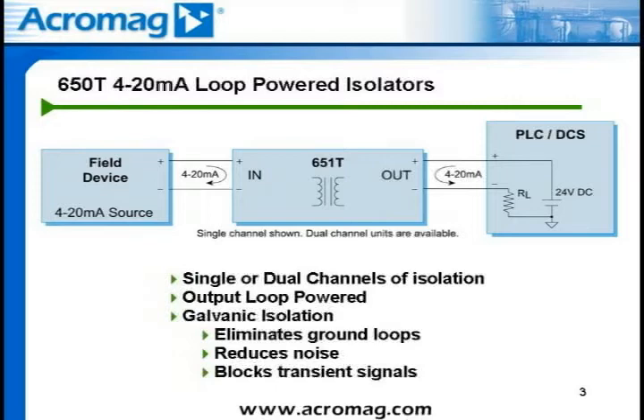One application would be where a field device is sourcing a 4 to 20 milliamp DC signal, and this signal is to be an input to a PLC which is also providing power through an internal 24-volt DC source. In this case, both the field device and the PLC are trying to power the analog loop — this will not work. A two-wire isolated transmitter is required to correct this power problem. The 651T will take the sourced 4 to 20 milliamp DC input signal and provide a sinking 4 to 20 milliamp DC output signal, enabling the 24-volt DC power supply at the PLC to power the input loop.